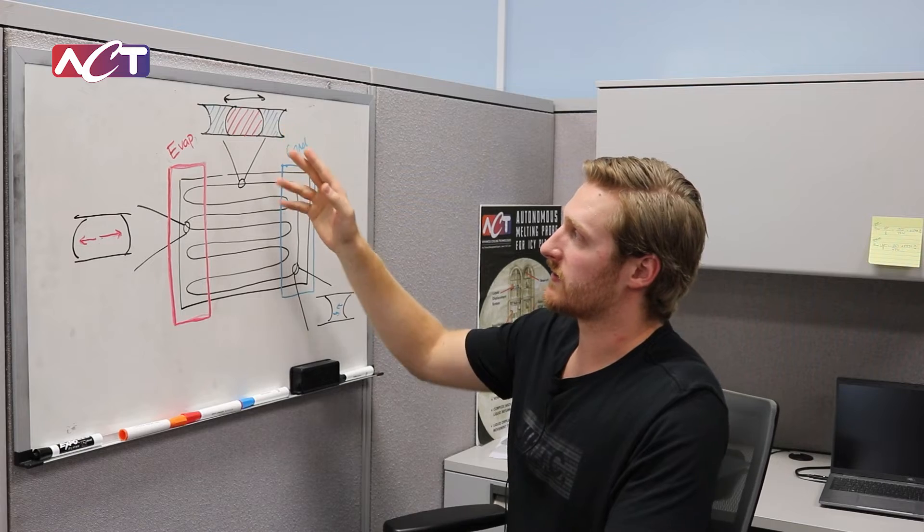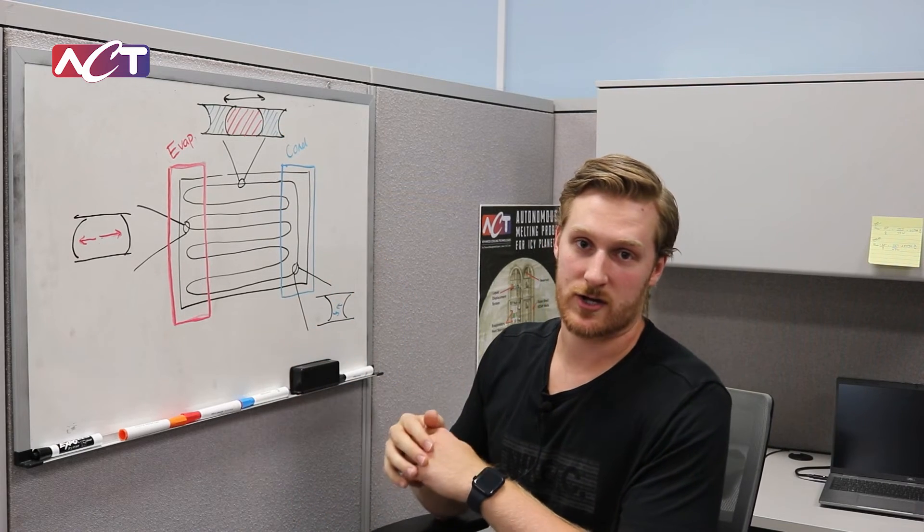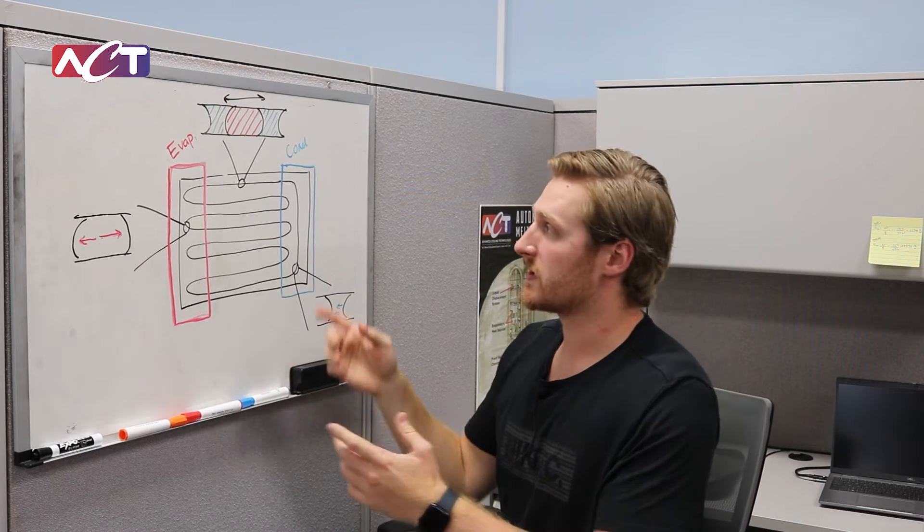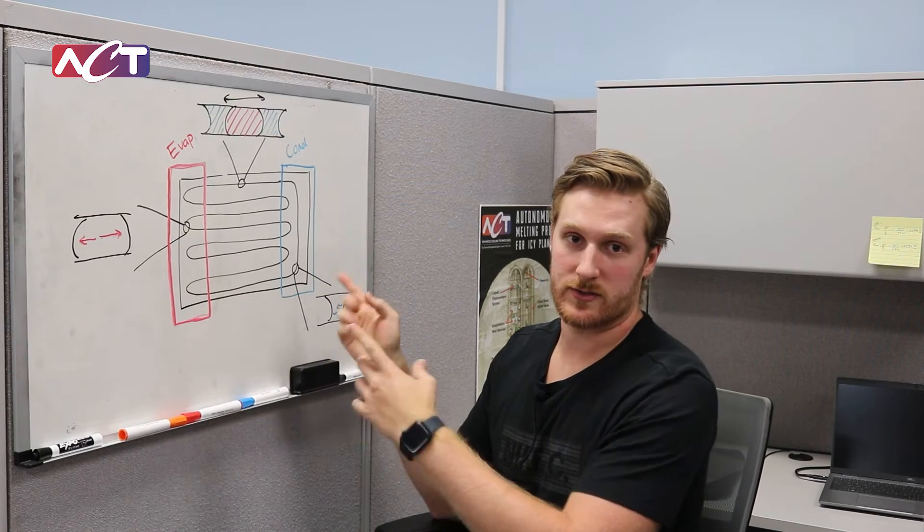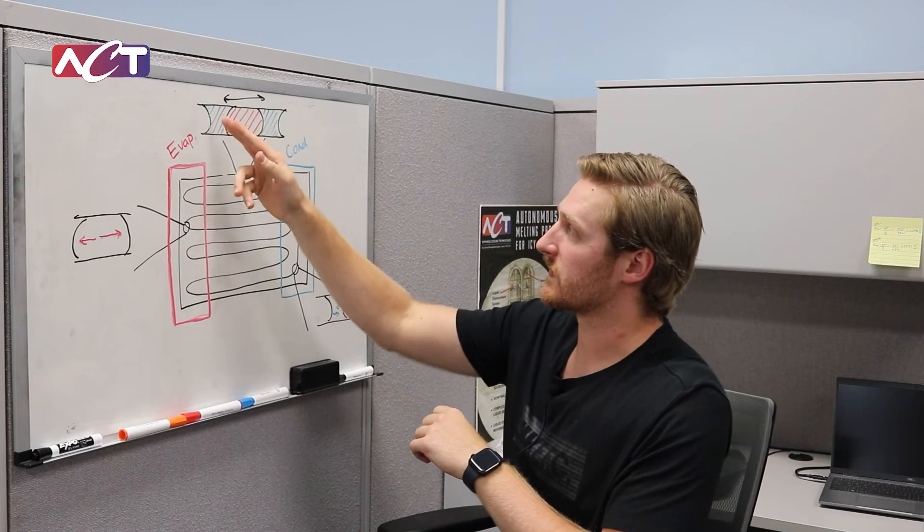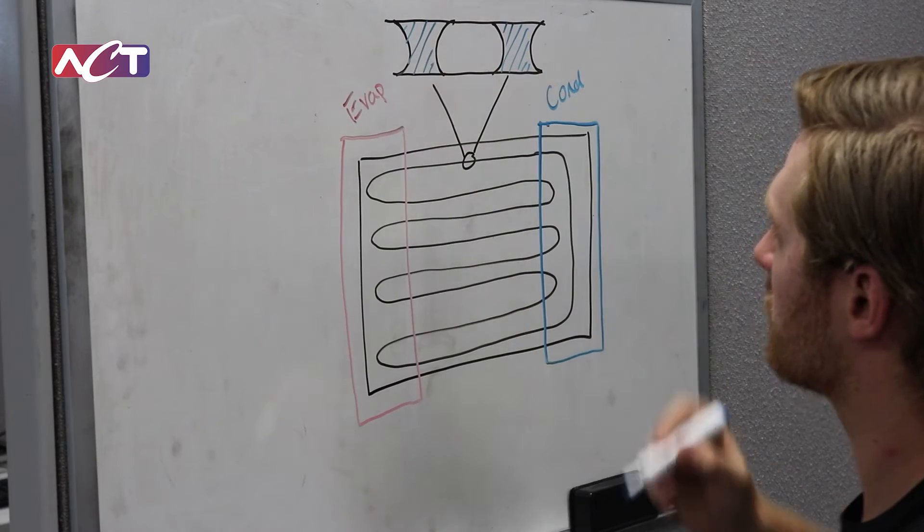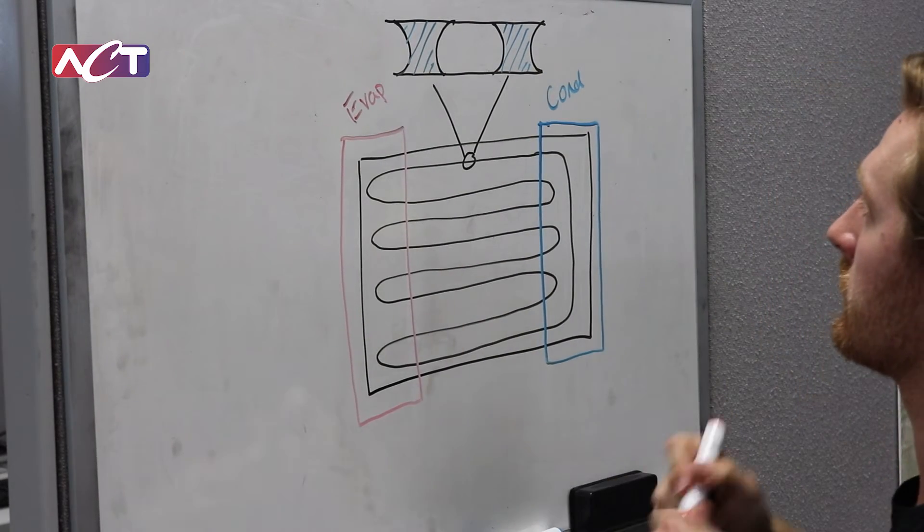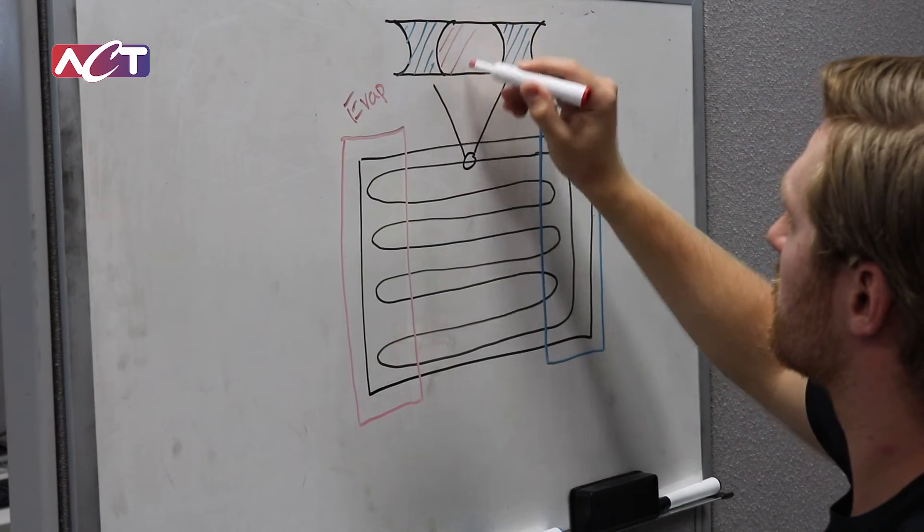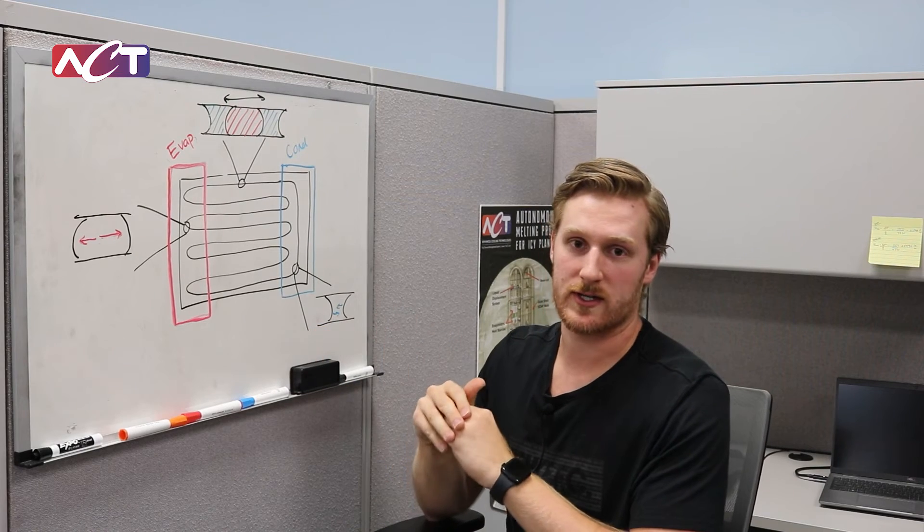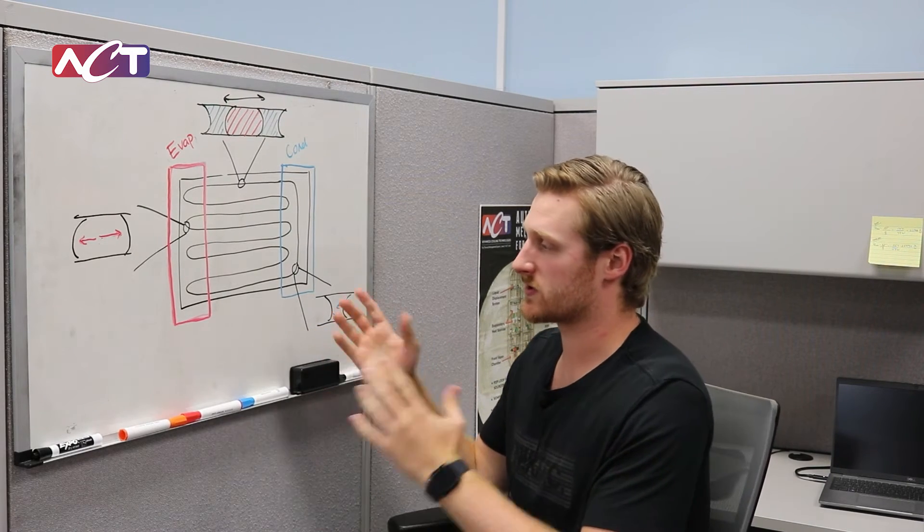Up above here I've highlighted that with the expansion and contraction of the fluid volume you get this oscillating motion where it goes back and forth. You have your liquid slugs and your vapor plug, and what this does is it helps efficiently transport heat from one location to the other.